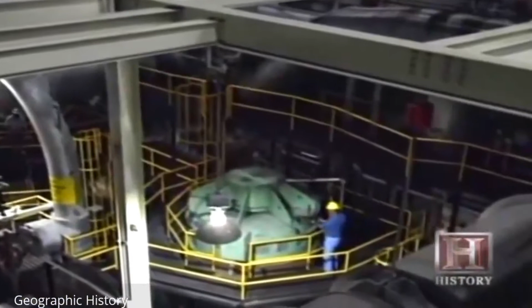Once the steam has done its work in the turbine, it enters the condenser, where it flows over 36,000 copper tubes containing water from the nearby Etowah River. The river water absorbs heat, condensing the steam back into water so it can be reused in the boiler. Hot river water is then cooled in 400-foot high cooling towers, each cooling 300,000 gallons a minute.